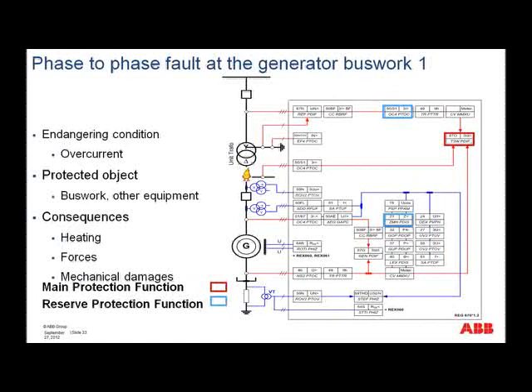Now, all we've done in this picture is we've moved the fault a little bit, so it's not actually inside the transformer, but it's on the buswork. And actually, it's really the same protections that need to handle this. So it's still in the zone of the 87O as the main protection, or the under-impedance protection, or phase overcurrent protection for current fed from the network.